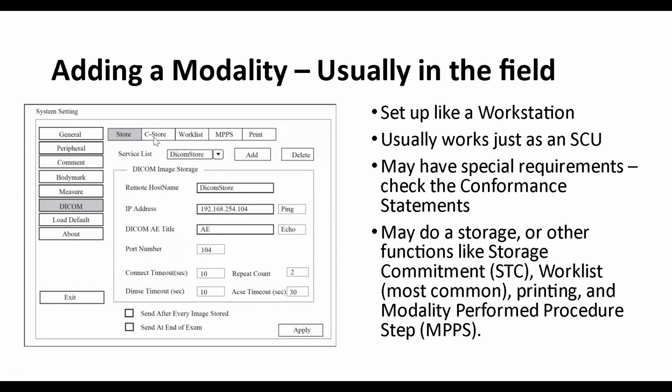With storage commitment, I say, I'm going to send it to this machine with this priority, but then I've got these machines as secondaries. I can change a path to go to my archive. Does that make sense? That's the basic structure. Again, I'm oversimplifying something and glossing over a lot of different settings, but think of it this way: I've got more than one server I can hit so that I can dump information to it.